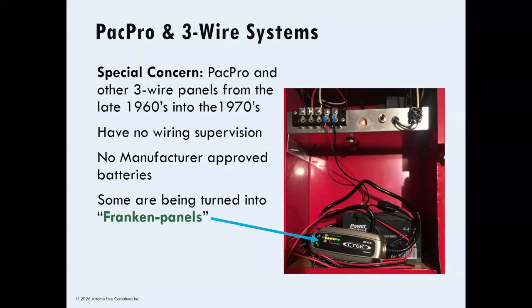In the case of the PacPro, the manufacturer-approved batteries haven't actually been manufactured for over a decade, and most service providers are using batteries that are not sanctioned for this panel. Some service providers have gone so far as to install other non-approved equipment into the panel, such as the noted charger that is plugged into the wall beside the panel, turning them into what we call Franken panels, which are not covered by ULC or insurance.